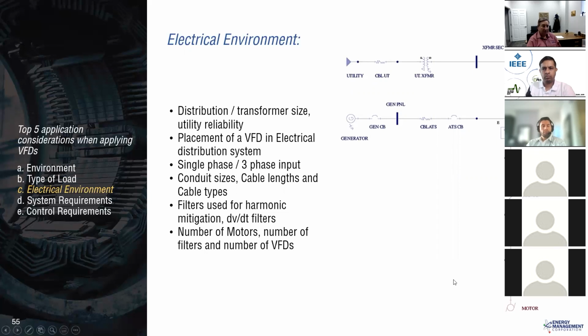Another interesting thing, we were just called in as a consultant for a project, I guess it was the airport in Honolulu, that was just completed for the baggage handling systems. And they had completed two before this. This third one, they actually used inverter duty rated cable because it was specified. And they had continual issues with DVDT failures, first turn winding failures. And they were using inverter duty motors. And we received a number of those motors and did root cause analysis on them.